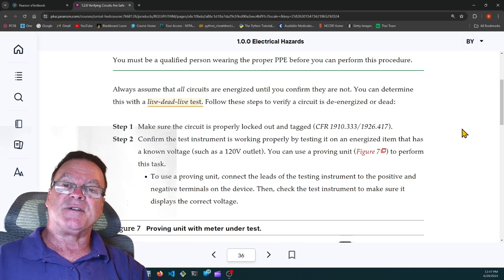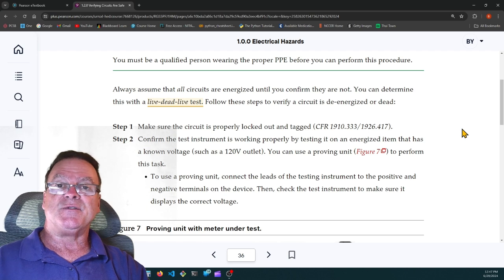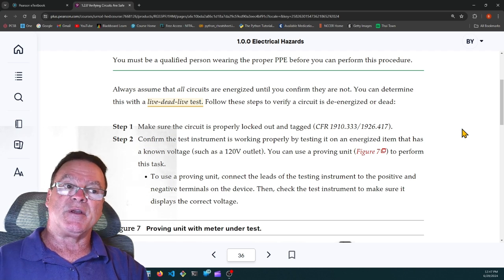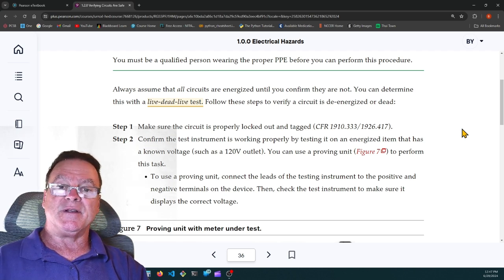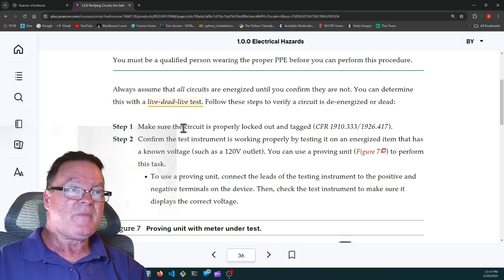Then you test it on the circuit. You want to make sure that it's dead. When it is, you lock it out, tag it out, but you still have to go back to a known live circuit and make sure that the meter is still functioning. It's a dead live test.